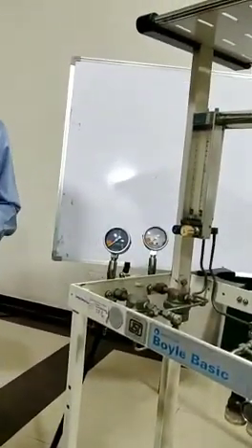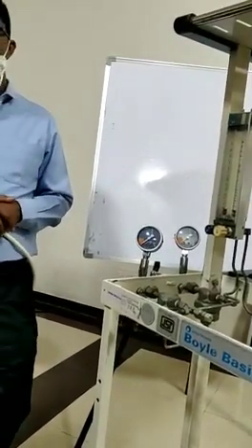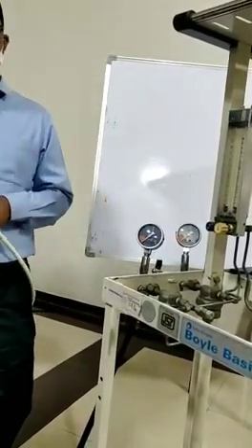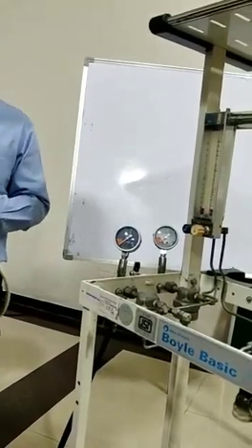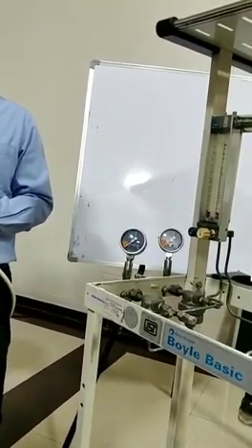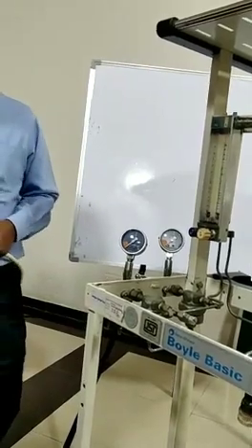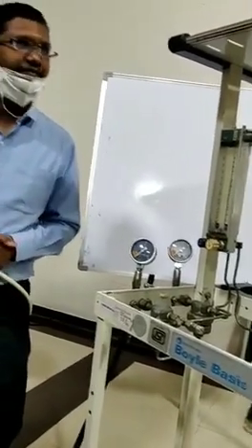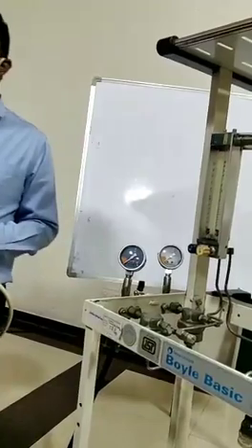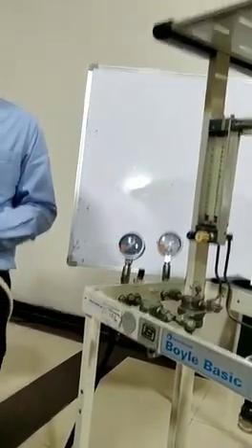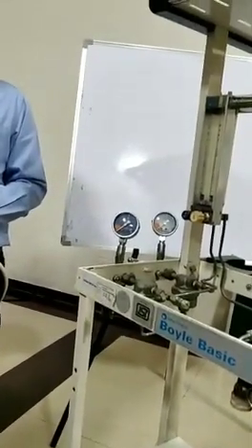So when you open the primary bank cylinders, all the cylinders of one bank will open simultaneously, and you have the primary pressure regulators directly in the manifold. In the manifold itself, the primary pressure regulators will reduce the pressure to the intermediate pressure system, which is 45 to 55 psi. Okay, that is the working pressure of the intermediate pressure system.